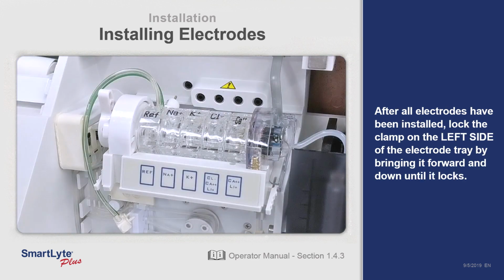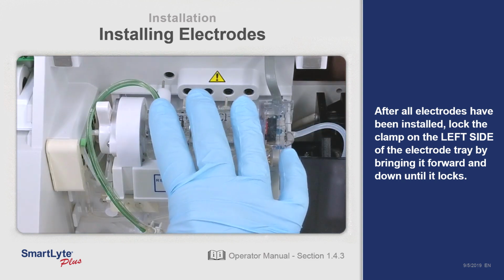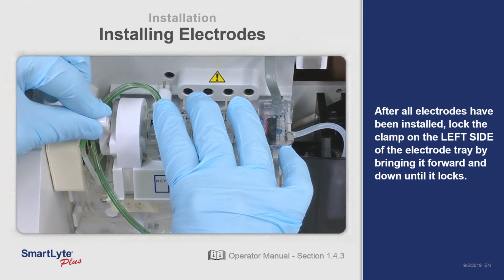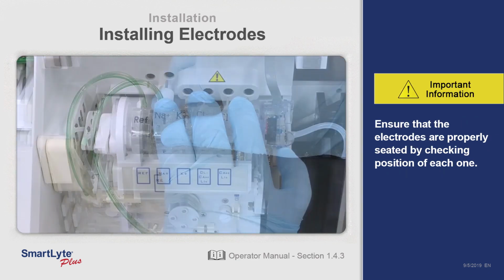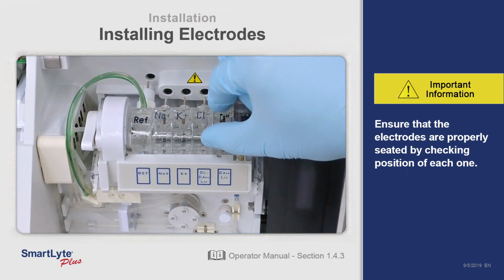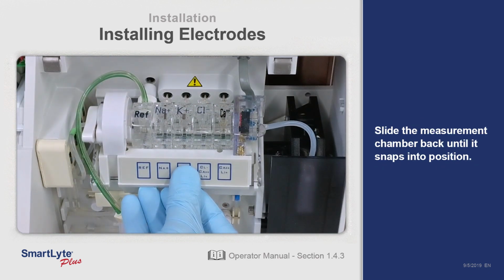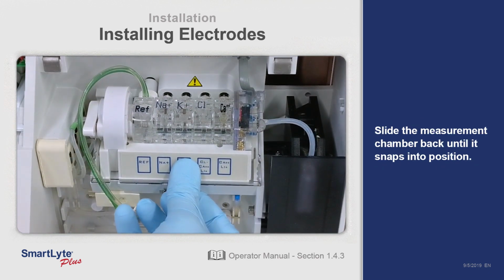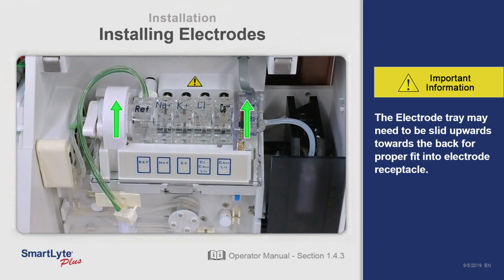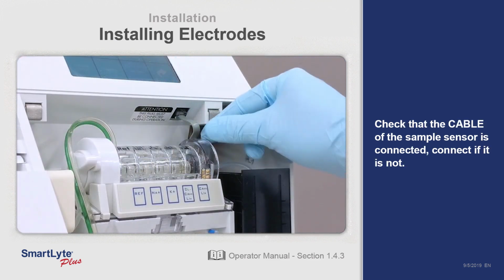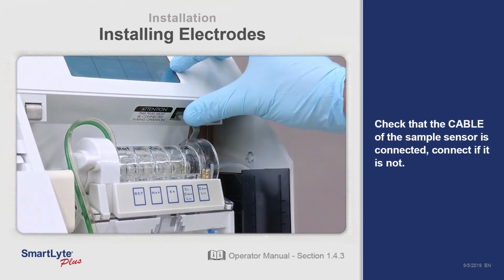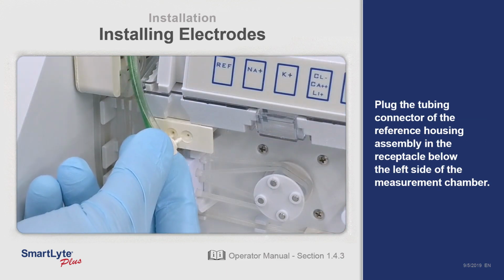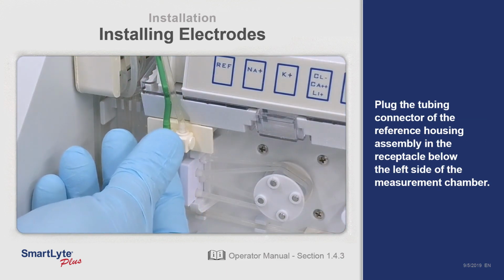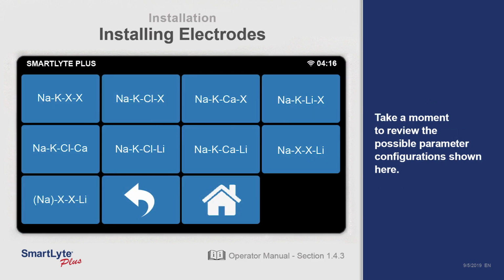After all electrodes have been installed, lock the clamp on the left electrode tray by bringing it forward and down until it locks. Ensure that all the electrodes are properly seated by checking the position of each one. Now slide the measurement chamber back until it snaps into position. The electrode tray may need to be slid upwards towards the back for proper fit into the electrode receptacle. Check that the sample sensor is connected. Connect if it's not. Plug the tubing connector of the reference housing assembly in the receptacle below the left side of the measurement chamber. Take a moment to review the possible parameter configurations shown here.